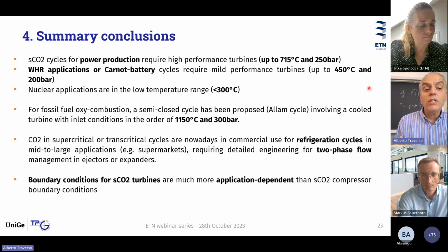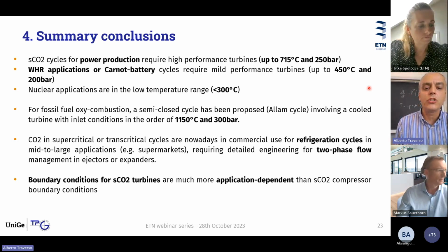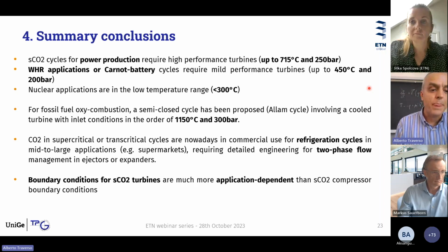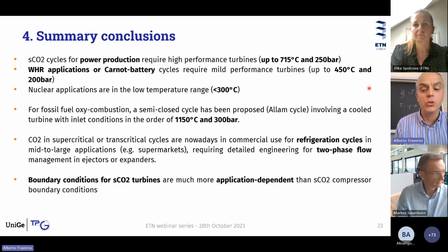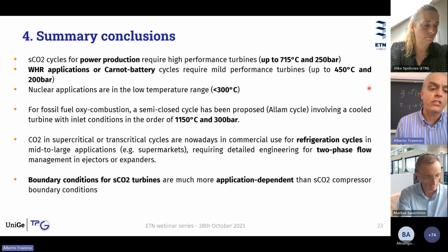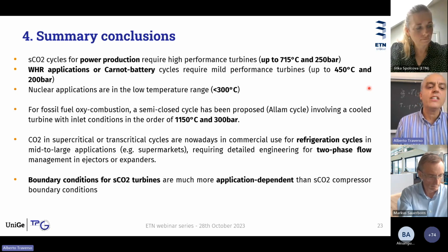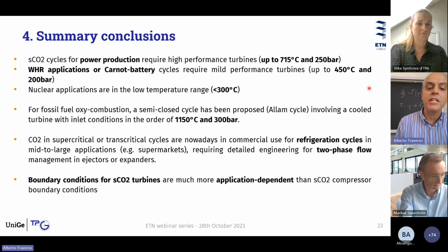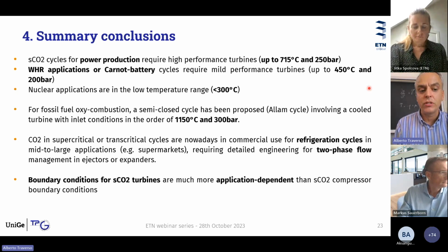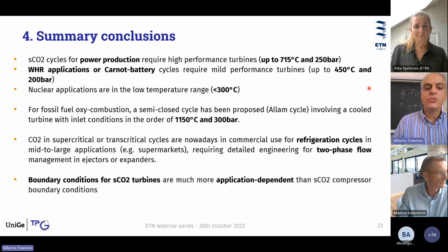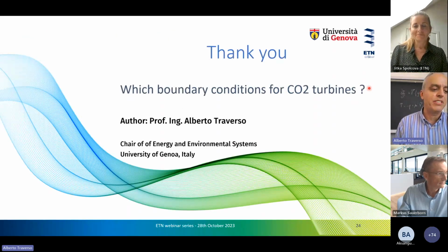If we look at the only supercritical CO2, or transcritical cycles commercial application, we can say that in refrigeration cycles, we have the need for reliable design tools for two-phase flow, especially in nozzles that can be used in ejectors or expanders. Ejectors are commercial, expanders are under study. Finally, general conclusion, boundary conditions for supercritical CO2 turbines are much more application dependent than the compressor boundary condition. And this was, I think, the main message from my presentation.